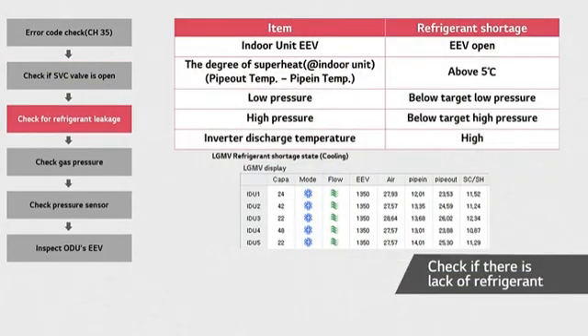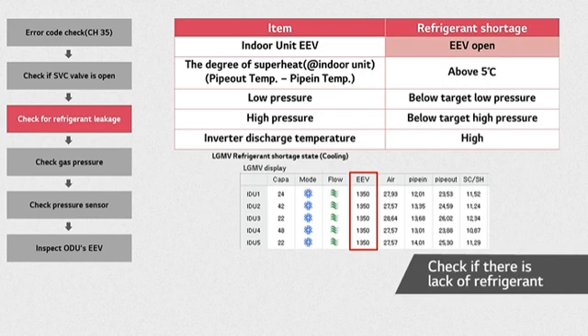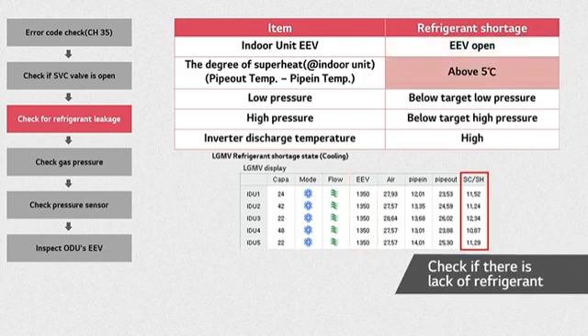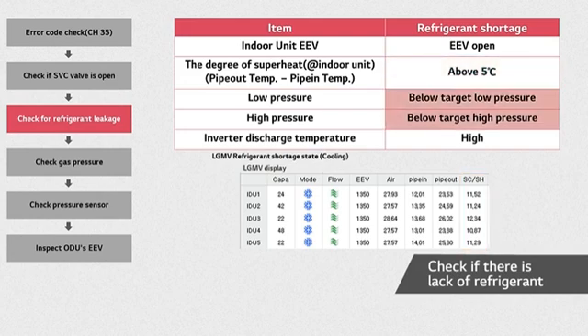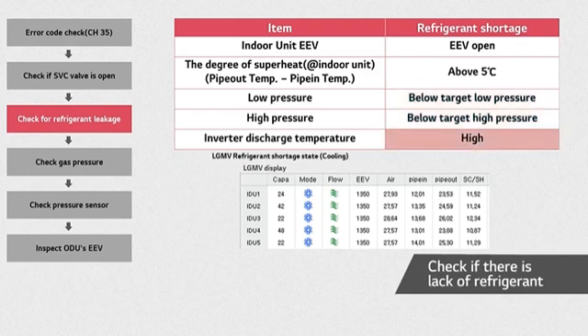In order to solve this problem, start by checking if the refrigerant is insufficient using LGMV. Through LGMV, you can also check the cycle. You can tell that the refrigerant amount is lacking when the indoor unit EEV is fully open and the degree of superheat at the indoor unit is above 5 degrees. Superheat is the difference between the pipe-out temperature and the pipe-in temperature of the indoor unit. Also, when both low and high pressure are below the target pressure for each, or the discharge temperature of the inverter is higher than usual, you can tell there is a lack of refrigerant.